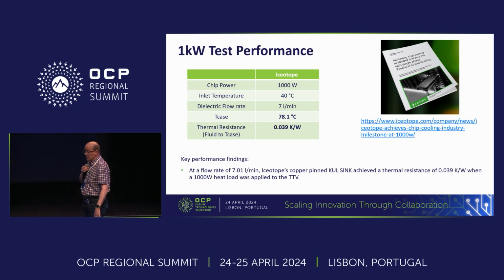So what happened? We ran 1 kilowatt into the TTV. The temperature we're feeding the dielectric into our heat sink was an easily attainable 40 centigrade, no need for any chilling. We're feeding the dielectric at 7 liters a minute. A quick comment on that flow rate: remember that's the dielectric flow rate circulated by the pump within our chassis. Decouple that in your mind from the much lower water flow rate you might be used to with a water-cooled cold plate. It's not a fair comparison, because we're reliant on the dielectric pump to feed our heat sink.